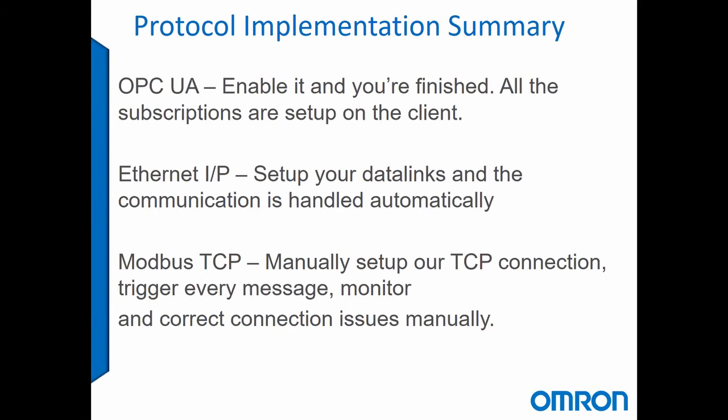Modbus, you saw what I had to go through. There's a lot of addresses and function codes, and then breaking the data you get into bits and bytes and multiplying it by constants to get the units where they need to be. Quite often you'll develop a custom data type according to what you find in that communication manual.